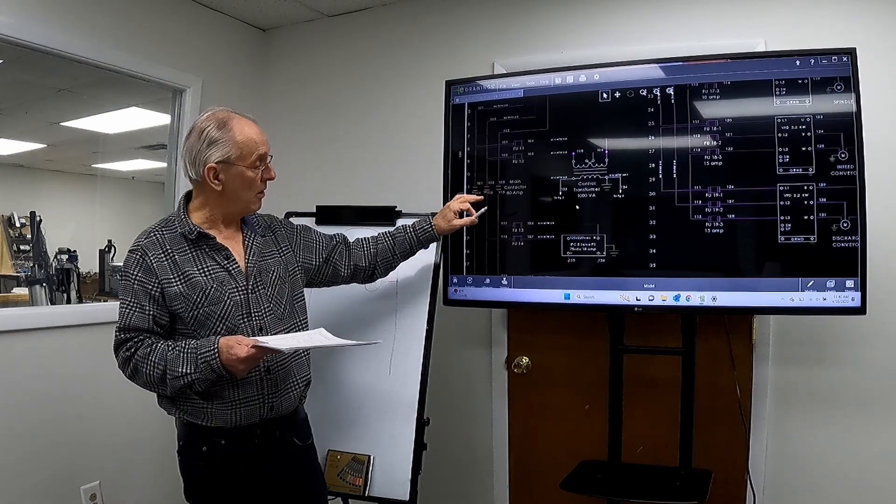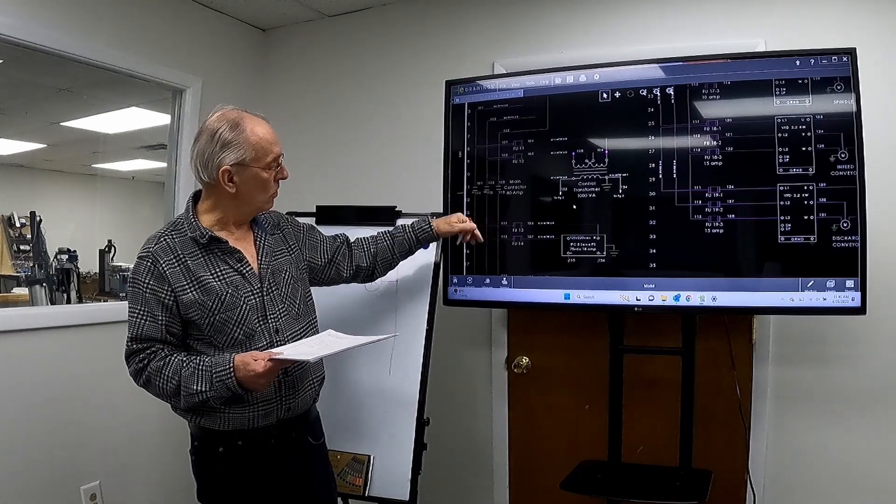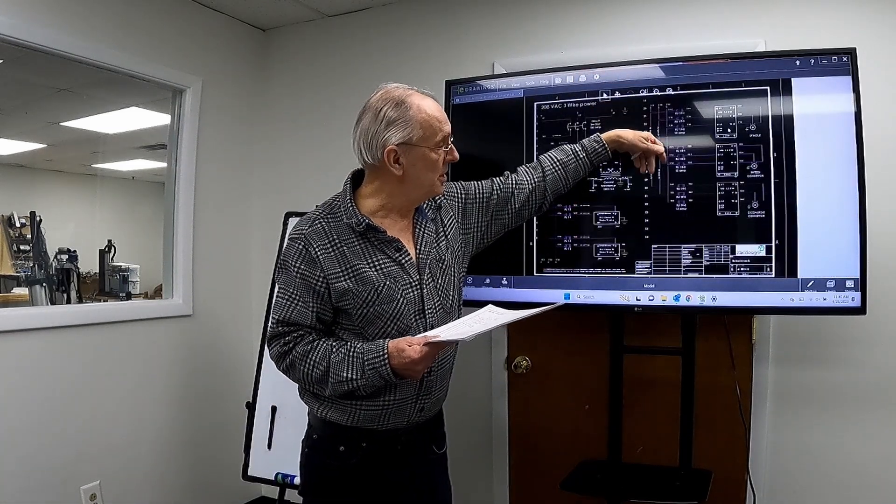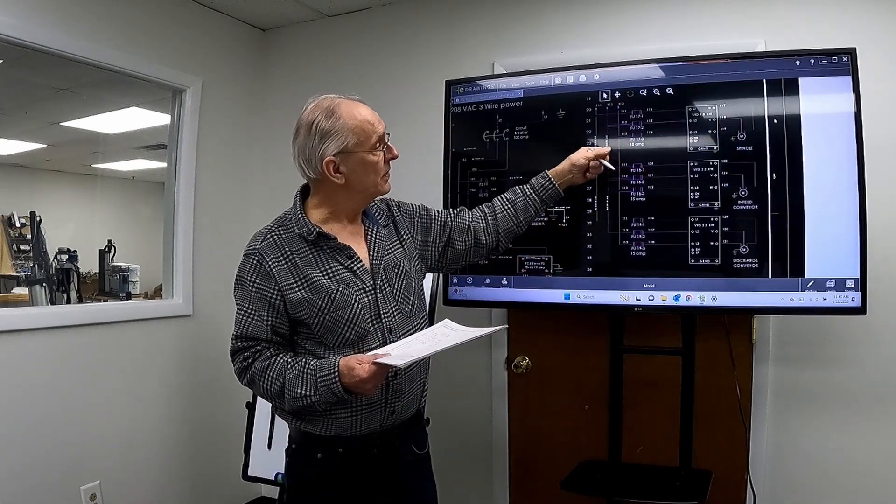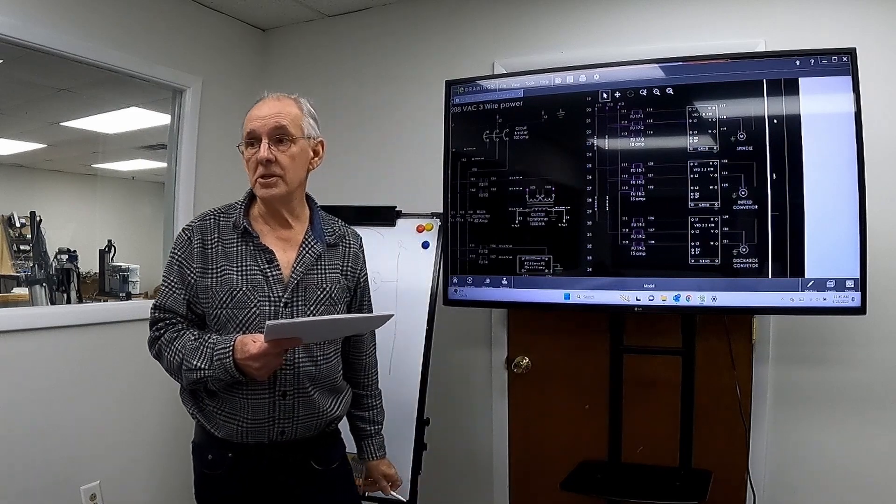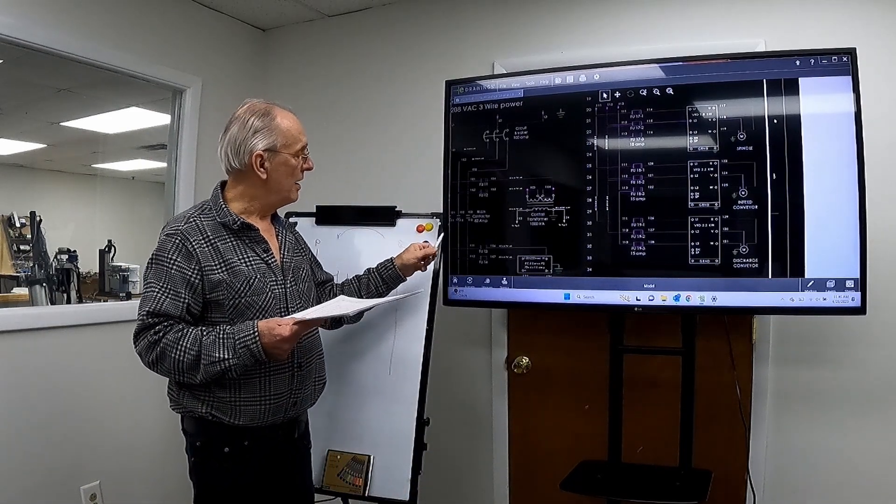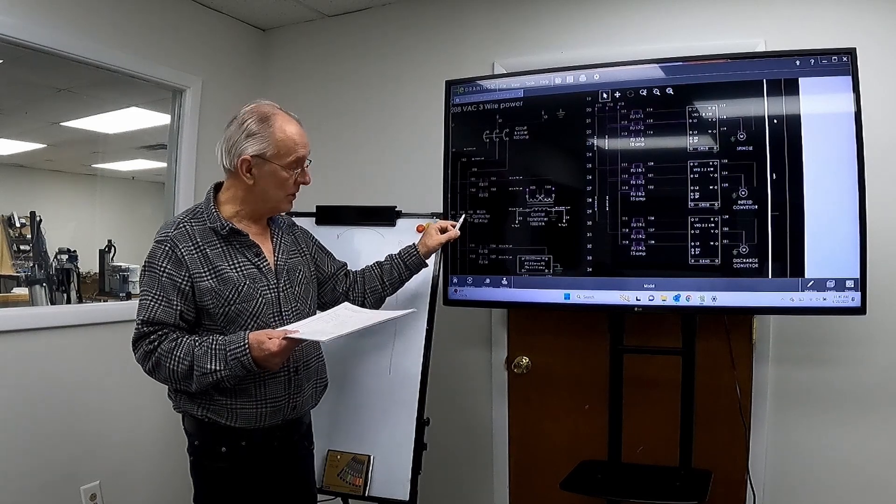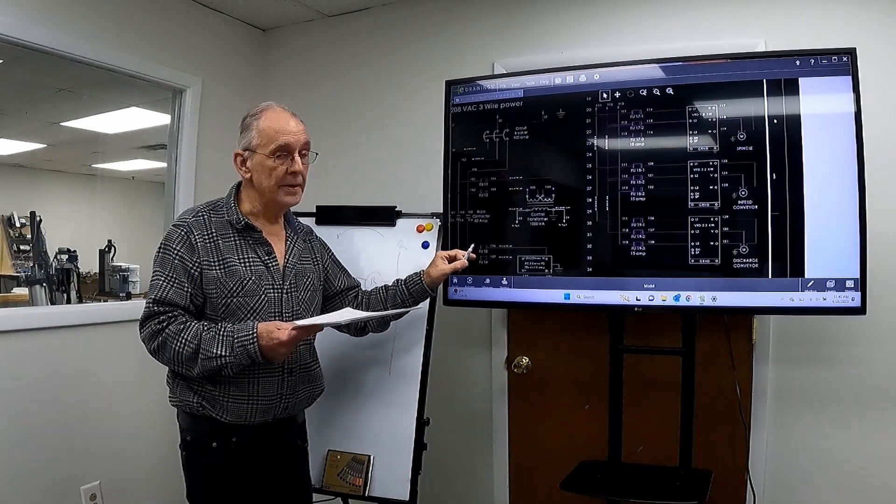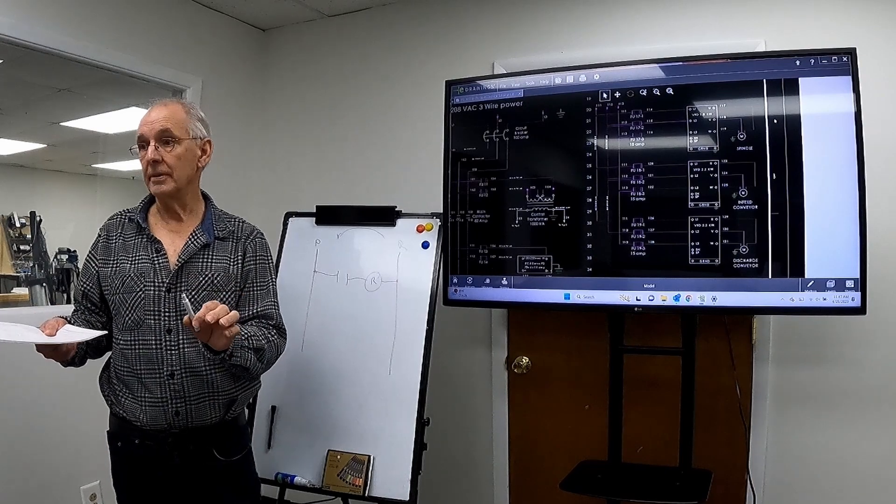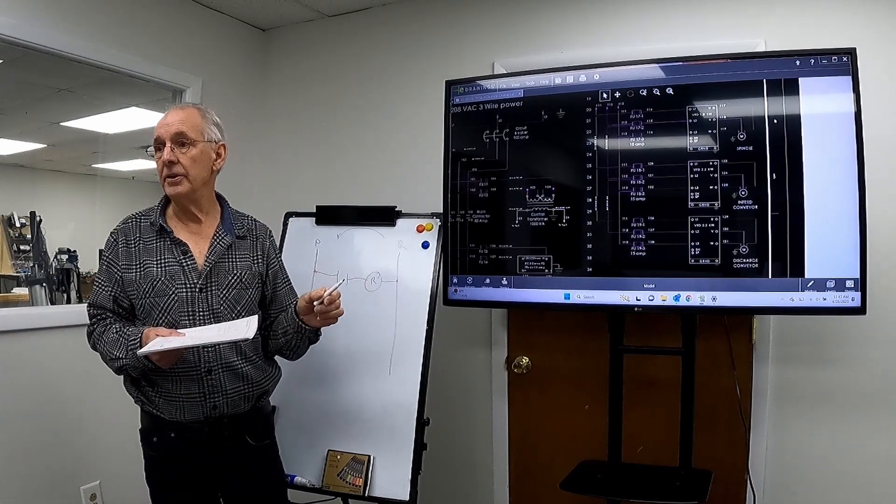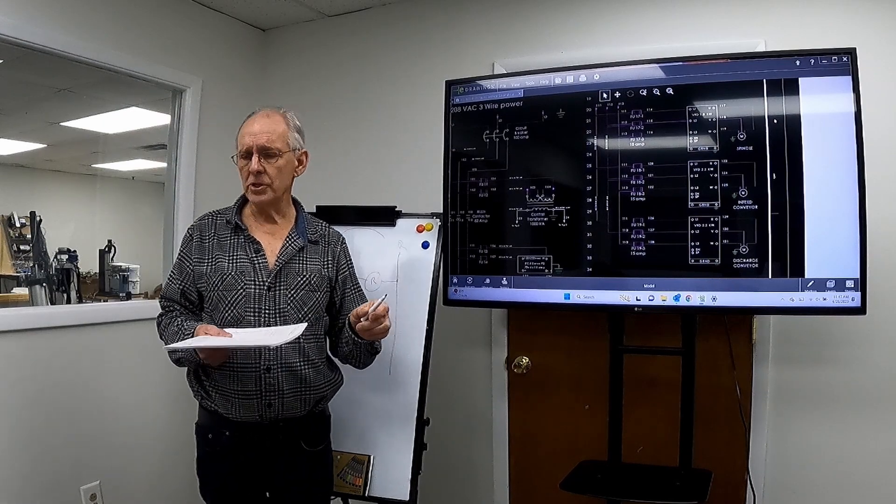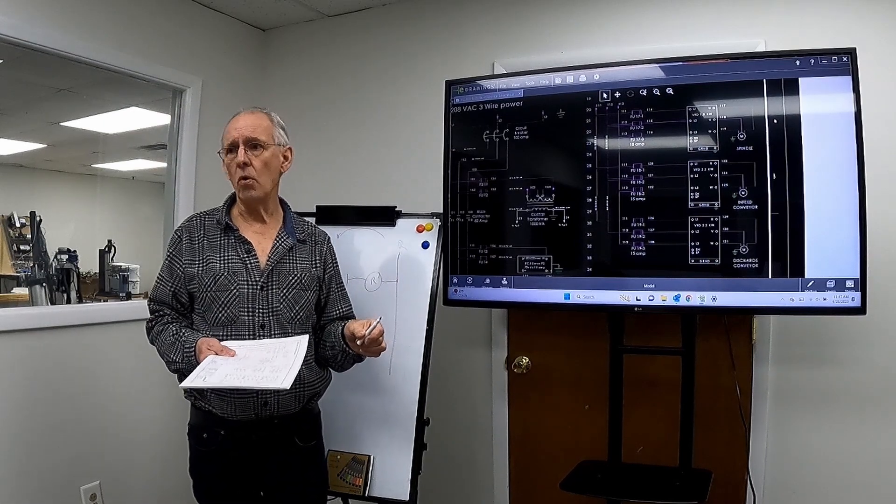Now what's it shut off the power to? Well, the drawing - these three lines go down and then they loop up to here. You see the numbers are the same. And so it shuts off all the VFDs, and there are other contacts on here. And I'll show you a little further down, and it shuts off everything that's an output, right? Which means that things like valves or solenoids and stuff like that, they also go off.